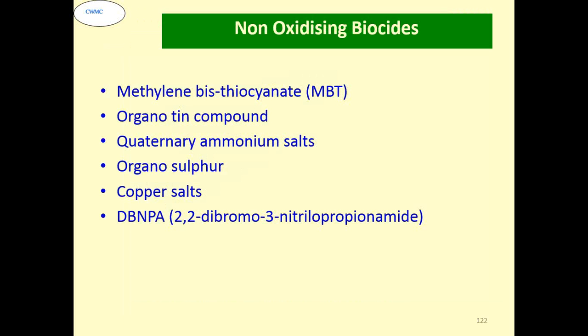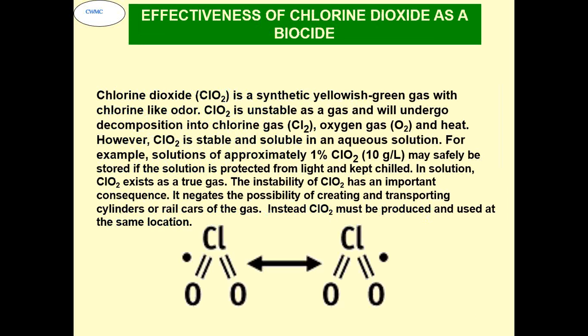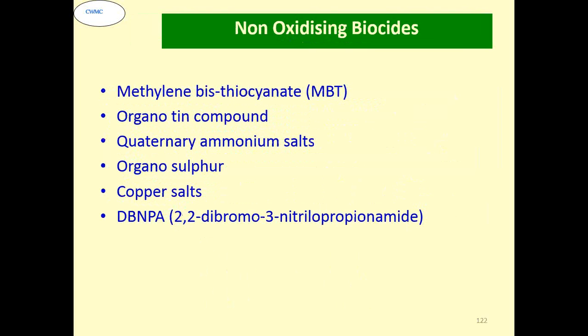There are certain non-oxidizing biocides which are used, like methylene thiocyanate, organotin compound, quaternary ammonium salts, organosulfur, copper salts, DBNPA, etc. Normally these non-oxidizing biocides are used as a supplement to the oxidizing biocide, and you are supposed to alternate biocides, because the bacteria become immune to one particular kind of biocide. So say in 2 weeks or 3 weeks, depending upon the system capability and the biocide capability, you change to a different biocide, and then after another 2-3 weeks you come back to the original one. Meanwhile, you continue supplementing with the oxidizing biocide like chlorine, which is the cheapest material as a biocide.